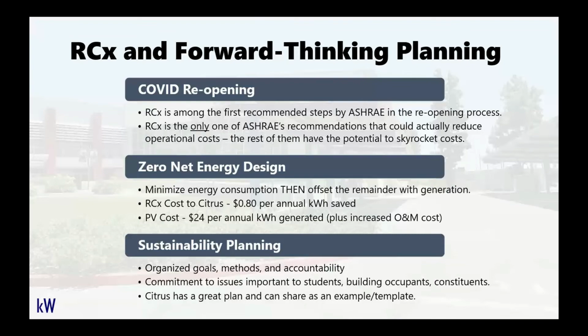With all that being said, retro-commissioning was very difficult. And one of the things that we had to do, David talked about the measurement and verification. He showed you the slides on how we corrected those energy inefficient measures with something that was efficient. Just a little caveat to that, because we were so successful on RCX1, that's what actually led to RCX2 and then on to RCX3. But the amazing thing is once we did all the measurement and verification, about a year and a half after the fact, for our first project, I got an email from an energy engineer out of Massachusetts. And lo and behold, his firm was actually hired by the California Public Utilities Commission to come out and do a reconciliation on our RCX1. So, I knew we were getting put to the test.